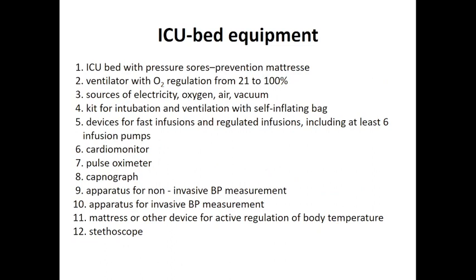Then it's written what should be at every patient's bedside. There must be special mattresses which prevent pressure sores, because patients in ICU stay there for a longer period of time and are at very high risk of pressure sores, so we need to prevent them. Ventilator, source of electricity, oxygen, air and vacuum, kit for intubation and ventilation with self-inflating bag, devices necessary for infusion, so electric infusion pumps, systems for regulated infusion, at least 6 pumps per bed.